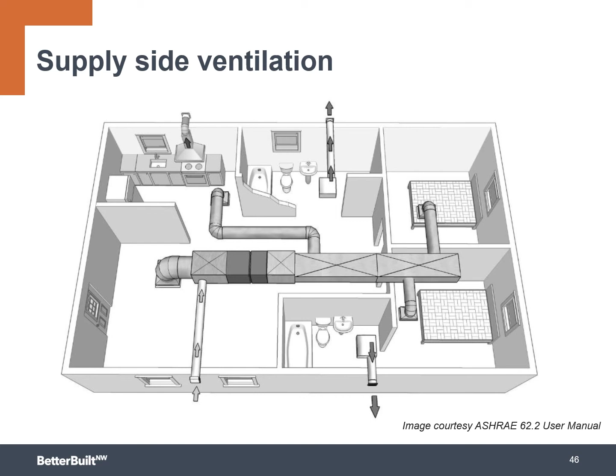So what is our lowest cost balanced ventilation approach? Well, guess what? We're basically taking the low cost exhaust only and combining it with a low cost supply only. So here we're matching a designated continuous fan for exhaust, and a fan or a duct bringing fresh air in to the return side of our central air handler. And we want to make sure that we commission them so it's about the same airflow. If the house needs 60 CFM, then we have an exhaust fan that's either rated to run at 60 CFM continuous, or maybe a couple of them at 30 each. And then we commission that the fresh air coming in when the air handler is running on low speed is around 60 CFM. And voila, there we go. We have a pretty decent balanced ventilation strategy here.